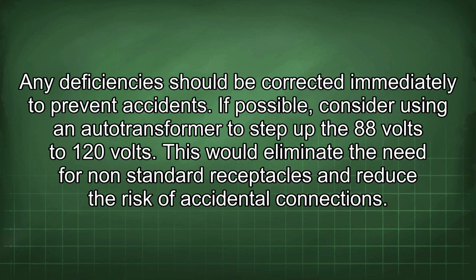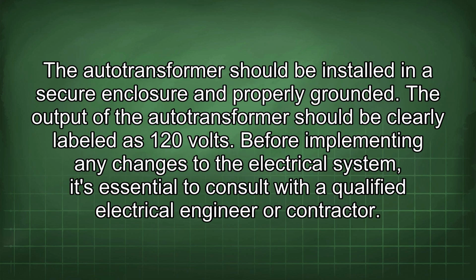If possible, consider using an autotransformer to step up the 88 volts to 120 volts. This would eliminate the need for non-standard receptacles and reduce the risk of accidental connections. The autotransformer should be installed in a secure enclosure and properly grounded. The output of the autotransformer should be clearly labeled as 120 volts.